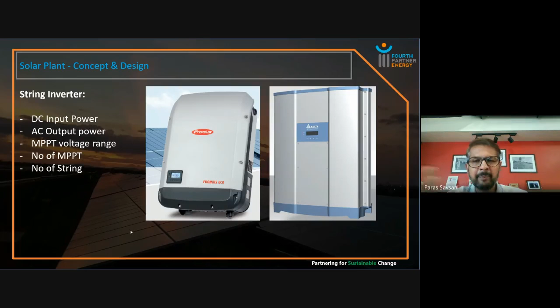The third scenario is installing a solar plant at a bigger ground-mounted site where power generation is huge. String inverters have a limitation on their maximum size. Right now the technology has advanced up to 100 kilowatt capacity in string inverters, but a year or two ago it was roughly limited to 50 kilowatt max. The second limitation is that for large megawatt-scale plants, using string inverters would require a large number of them.